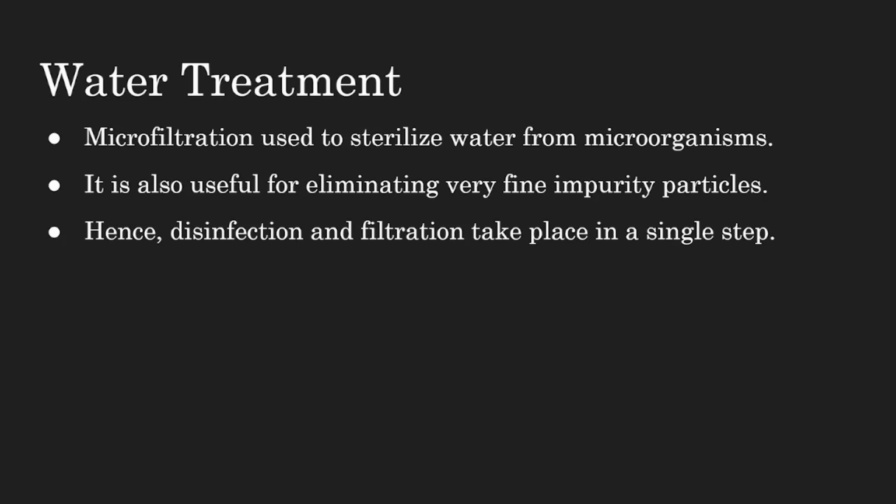It is mainly used to sterilize the water from microorganisms like viruses and bacteria. Some of these microorganisms are harmful to human health and also immune to conventional disinfectants like chlorine. Microfiltration helps to get rid of such organisms. It is also useful for eliminating very fine impurity particles, which is useful to remove turbidity from wastewater. Hence, disinfection and filtration take place in a single step while using microfiltration.